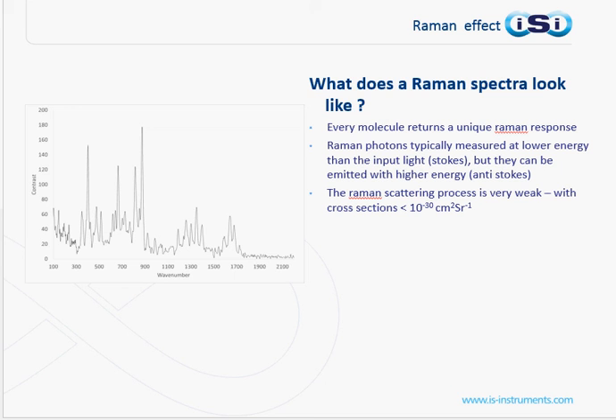The main problem with Raman systems is that the scattering process is weak, with cross-sections below 10⁻³⁰ square centimetres per steradian. This is significantly lower than absorption techniques, for example, and this has limited market take-up. The strength of the Raman return is directly proportional to the inverse of the input laser light wavelength raised to the power of 4. Therefore, in principle, using shorter wavelengths gives stronger returns.